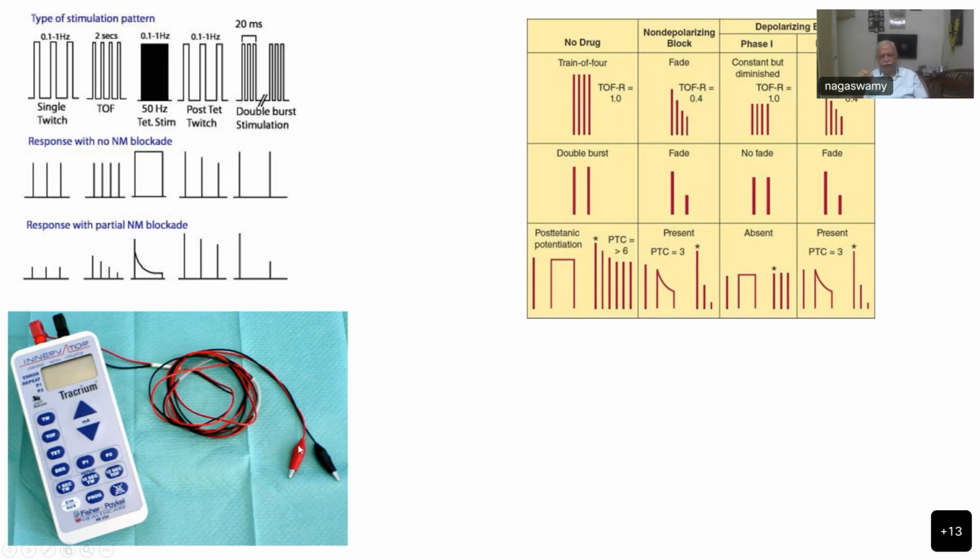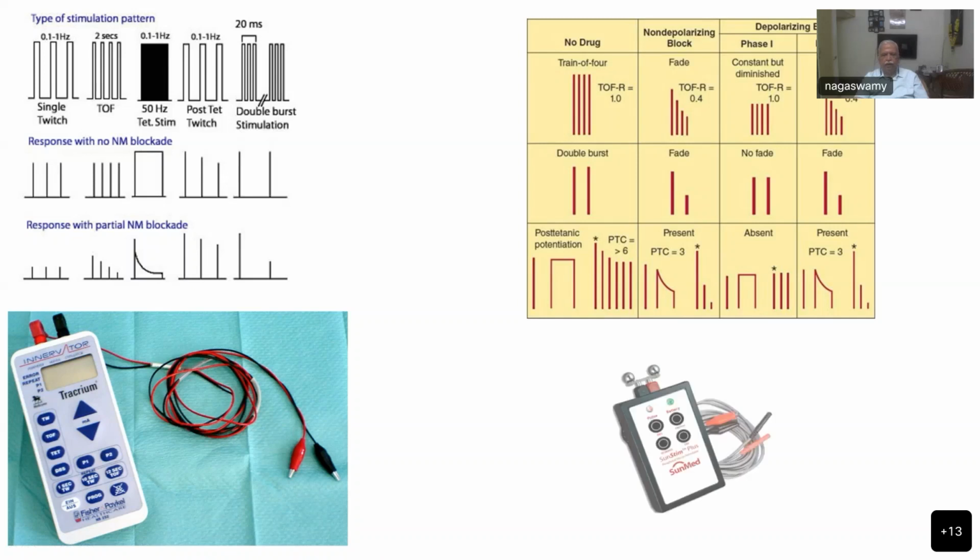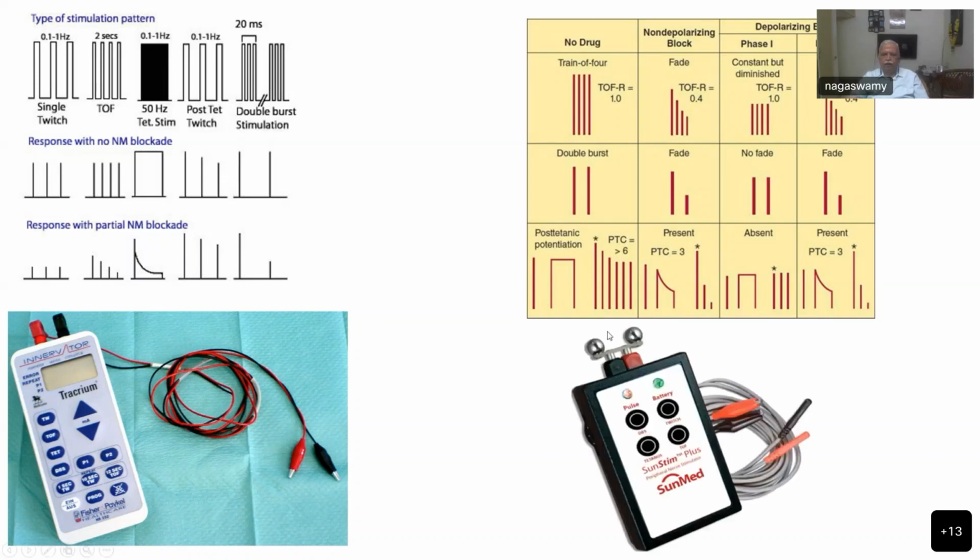See, when you press that, it will open. And when do you use this? This is used when you attach an ECG electrode, so you just clip it on. So this is called the crocodile clip of the electrical lead. And this is the ball electrode. Okay, this is for single-time use. If you want to replace it, you have to remove this and then attach this, where you also have crocodile clips available for continuous measurement.